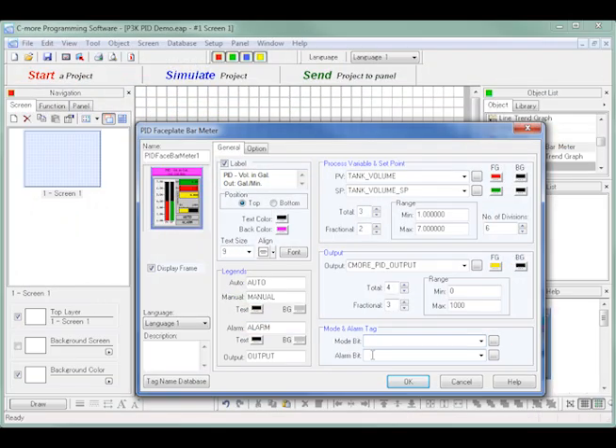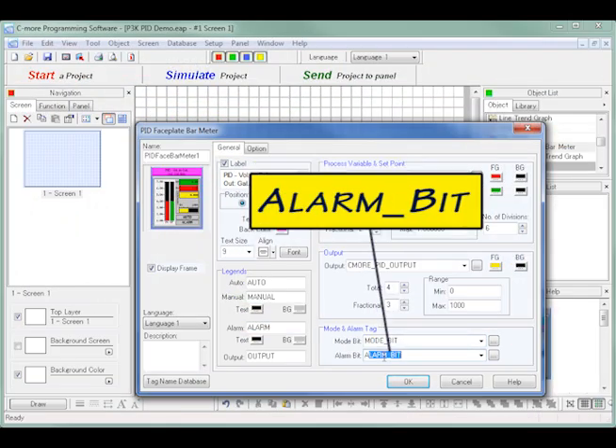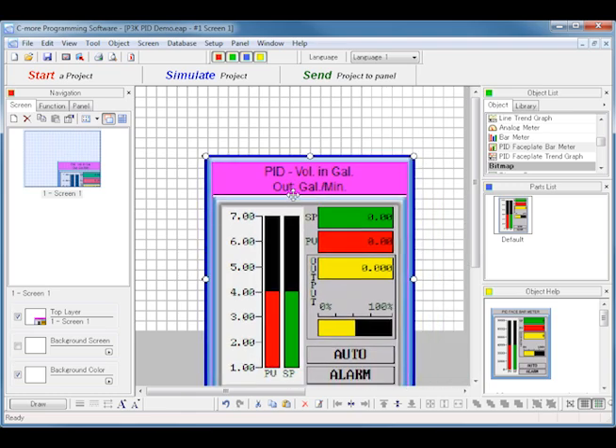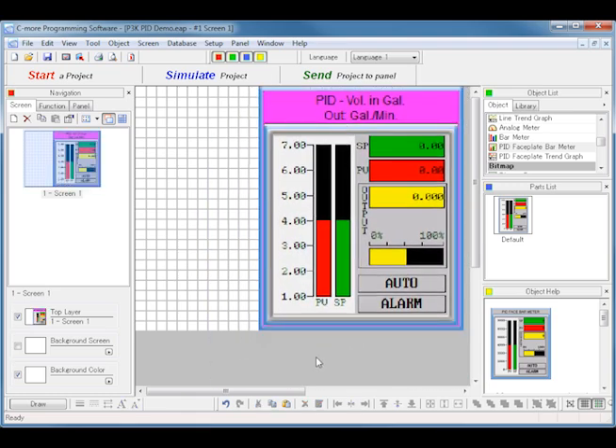Finally, I type in the mode bit and alarm bit tag names that we control on our ladder logic to show if the PID loop is either in auto or manual mode, and if there is an alarm condition, such as overflow. Next, I press the OK button and position the PID faceplate to the right hand side of the screen grid.